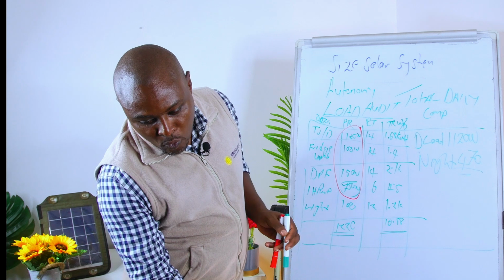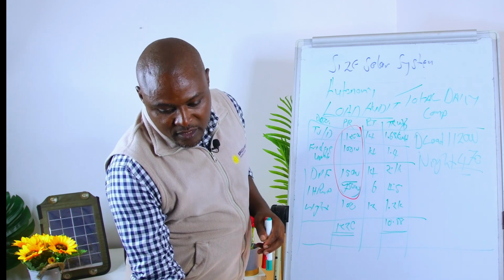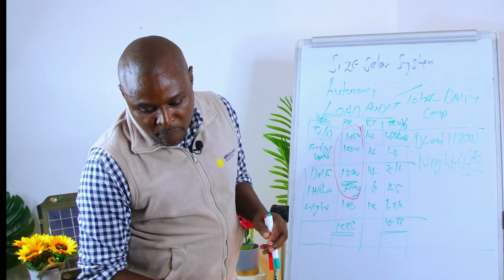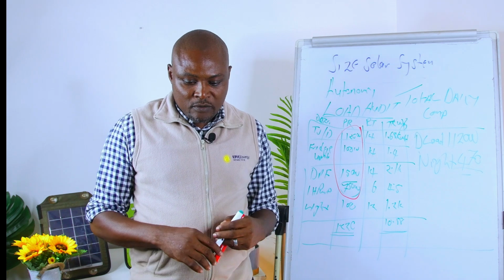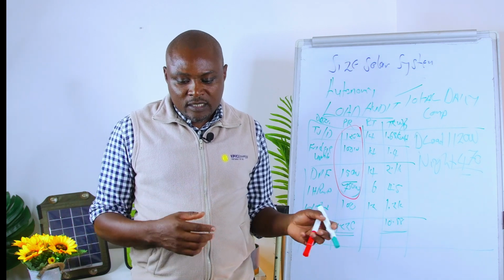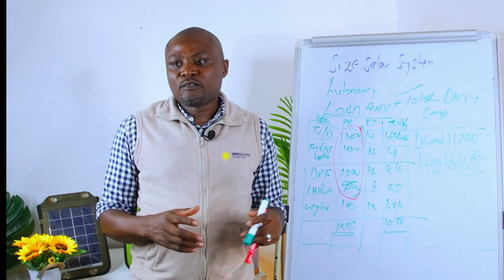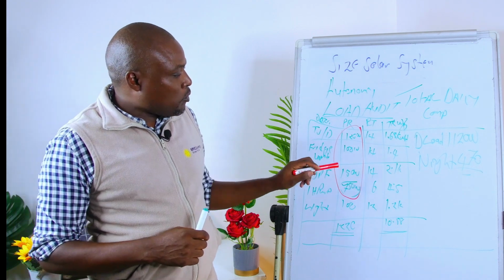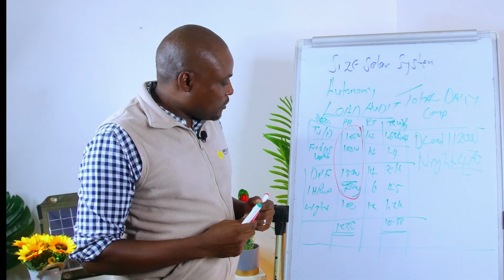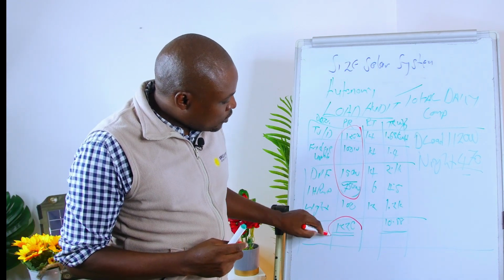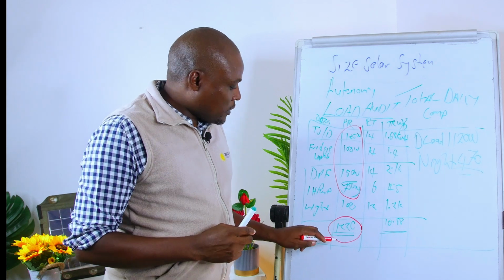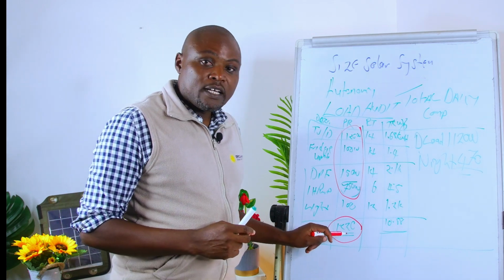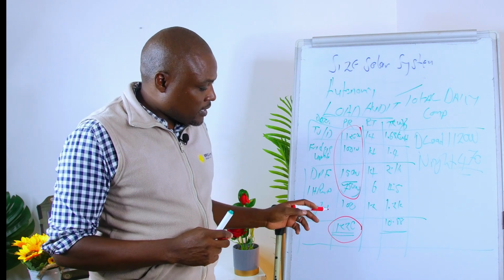So once you know the load, once you know the power rating, and you have all this information, we size the system from two fronts. So we are sizing the system from the capacity and from autonomy. So if you want to know the size of the inverter that we need, that is going to power this load here, it means we are talking of anything in the range of 1,500 and above.